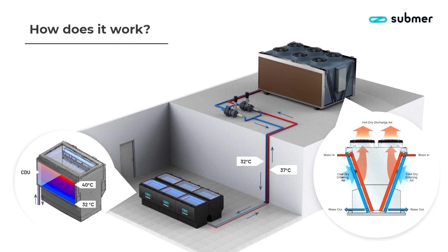How does it work? There's a water loop connected to the immersion tanks. The tanks transfer the heat through the cooling distribution unit, or CDU, which captures the heat from the IT equipment and transfers it to the water loop. That water loop runs either outside, or we have a heat exchanger in between to activate energy reuse. The whole idea is a very simple installation with a redundant pumping system for the water loop, like any data center has today.